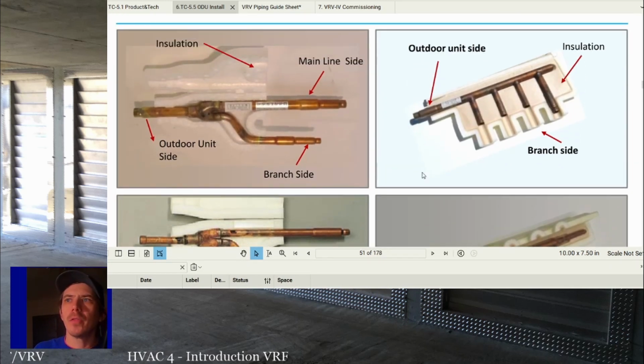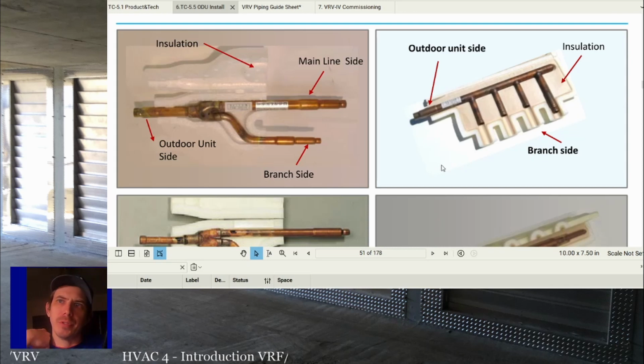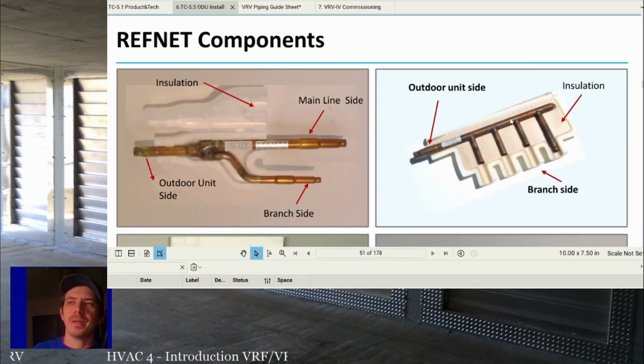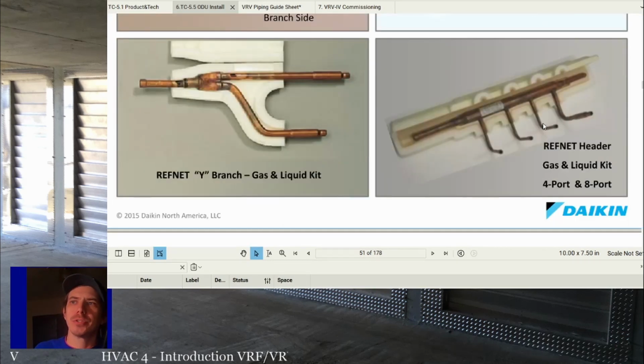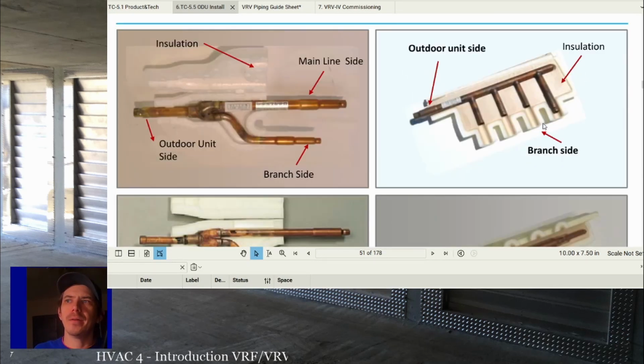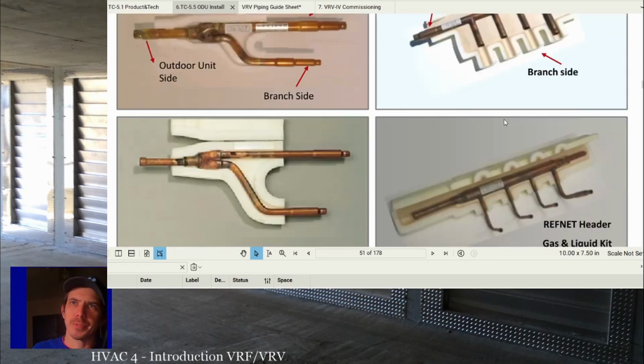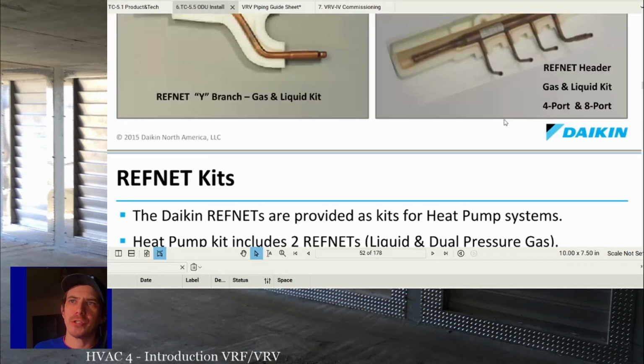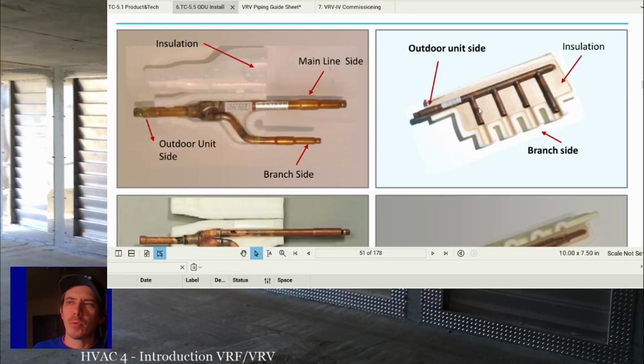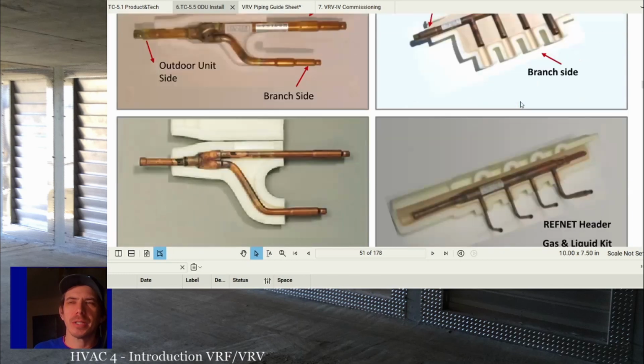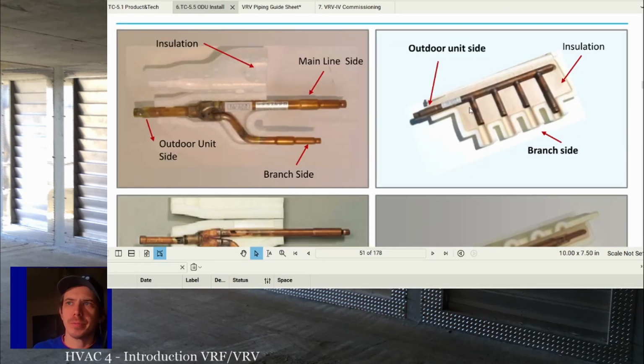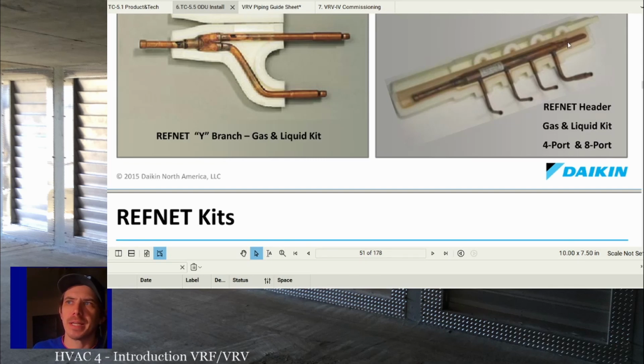They look really similar. Now the other ones you have, and again, this is where you get into the less common situations. Doesn't mean they don't get used. It's just, out of all the jobs I've seen, they're rarely spec'd. Is the multi-connection ports that look like regular T's. So what you'll have, if I remember right, and I'm not 100% sure, maybe we'll see and it will get some kind of verification, but if I remember right, this is going to be your suction and this is going to be your liquid. In general, if you're using these on suction, and I remember at one point they said you just couldn't do this on suction, but I think they started allowing you to do it. But if these are on suction, they have to be horizontal. These on liquid all need to be facing down and then running.